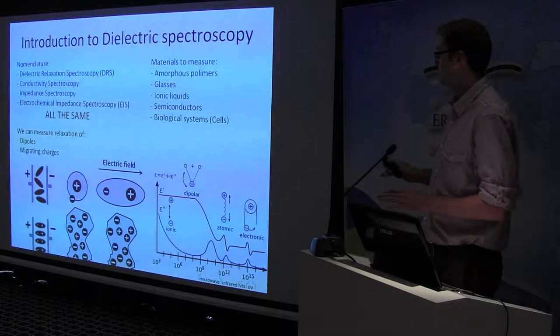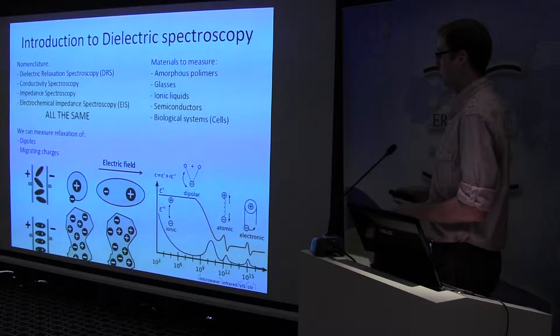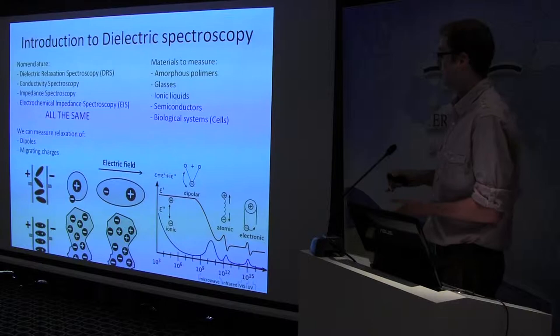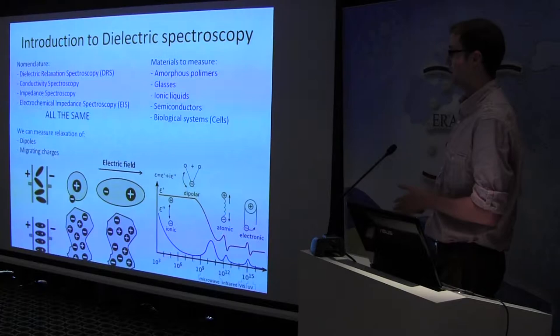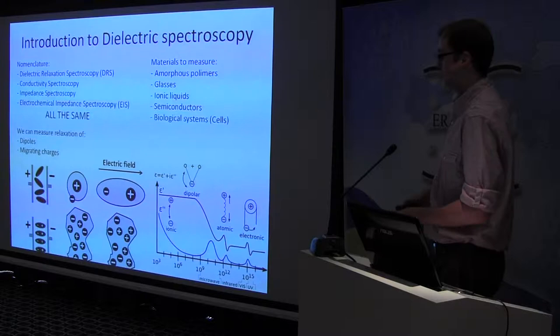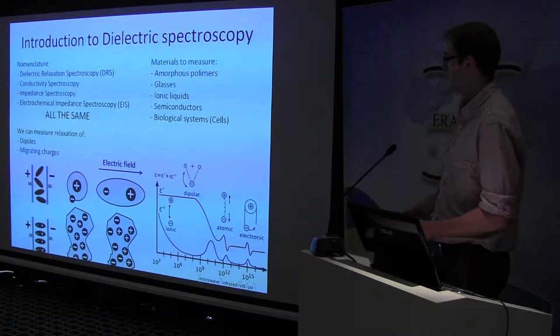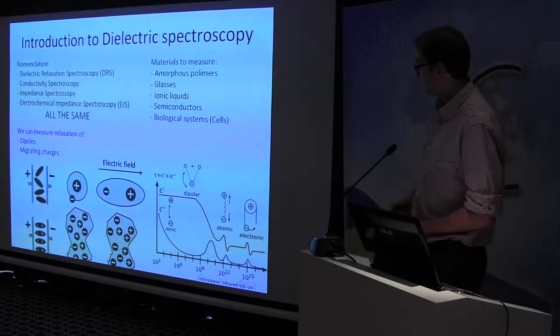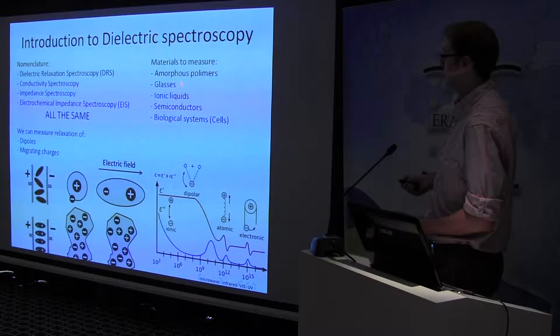Maybe some of you are not familiar with this technique, so just a few words about it. In dielectric spectroscopy, you apply an external sinusoidal voltage to polarize your sample. And then you measure the relaxation of dipoles or migrating charges in your sample. Here you can see some basic polarization processes and here you can find some materials that can be examined by this technique. For example, amorphous polymers, glasses, ionic liquids, semiconductors and even biological systems.